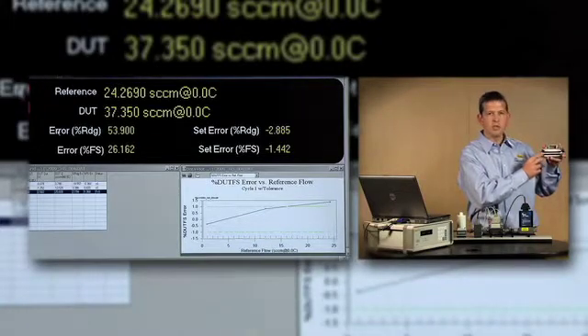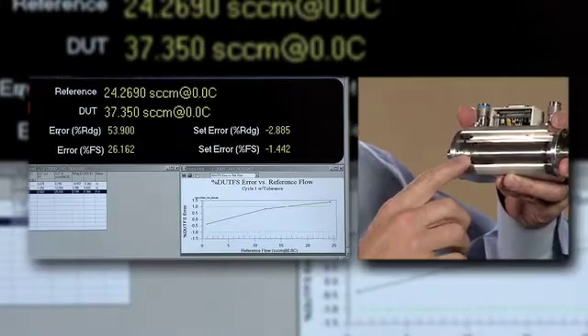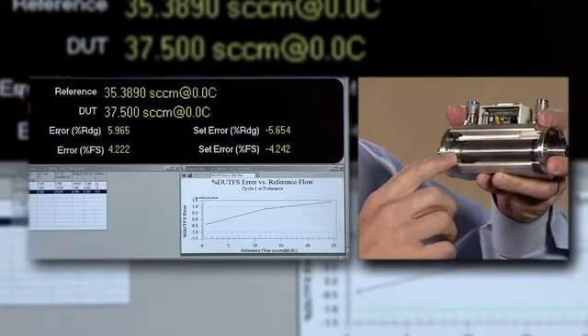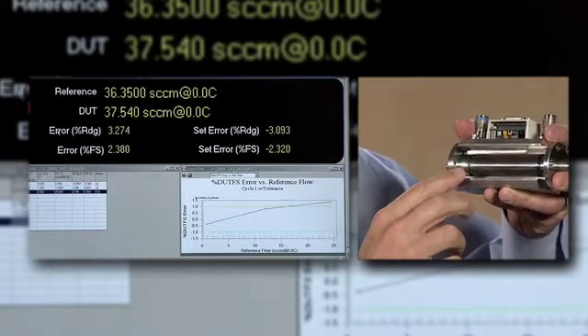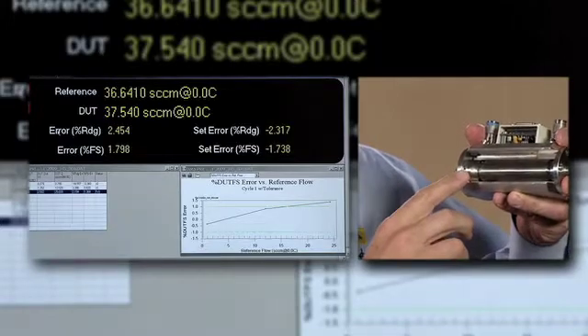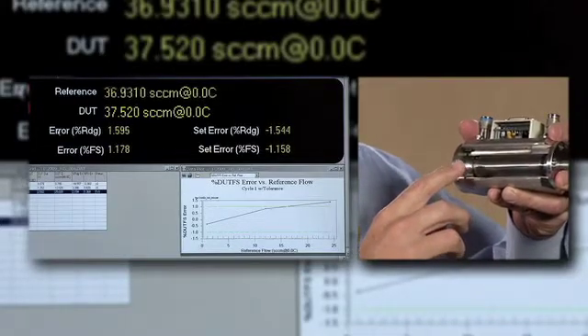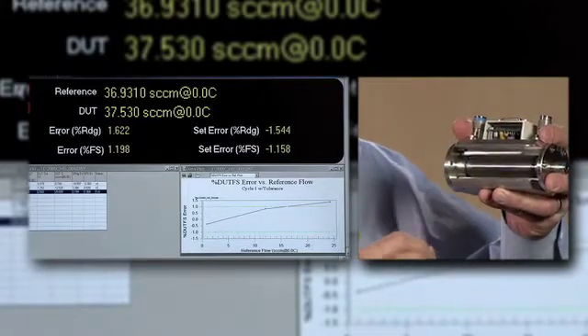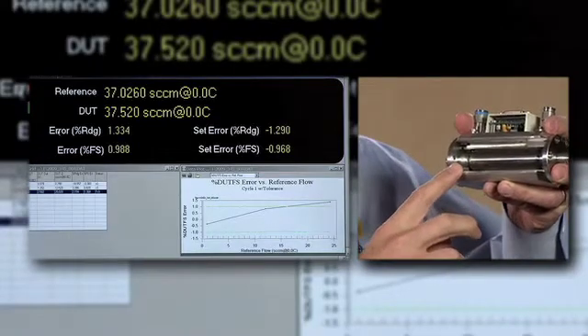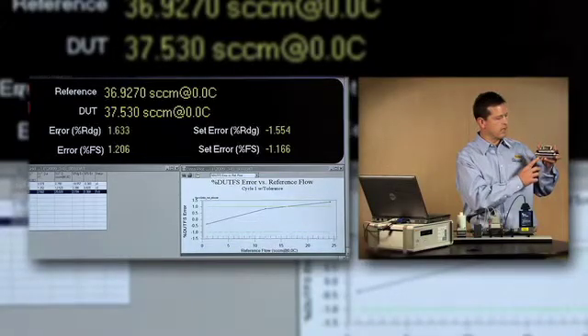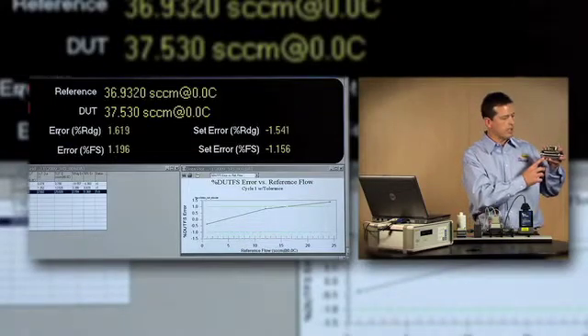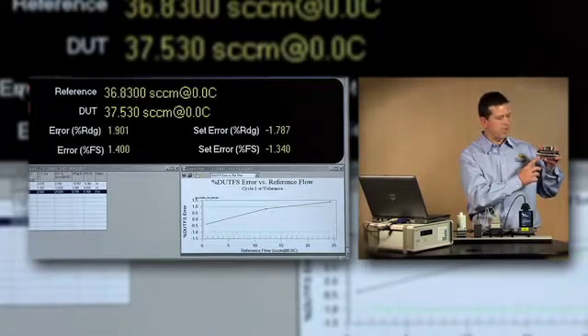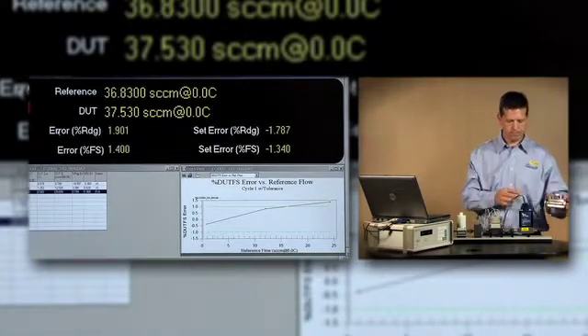And it also allows us to measure the temperature accurately by forcing the gas to take on the temperature of this relatively large Molbloc body made of stainless steel, which acts as a heat sink. The temperature is measured then by platinum resistance thermometers embedded into the body of the Molbloc. And both the temperature and pressure signals are collected and passed on with this electronic board on the Molbloc, and the calibration coefficients are stored on an EPROM on the electronic board as well.